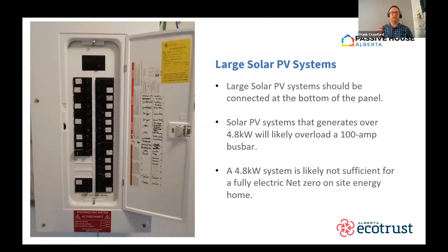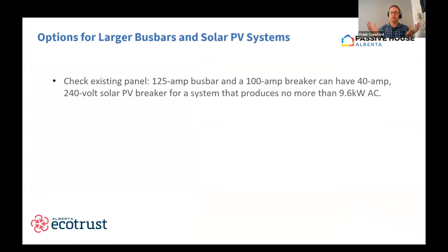Basically, the code clauses say that if you want to attach a solar PV system that generates more than 4.8 kilowatts of AC power, it will overload that 100 amp bus bar. And that 4.8 kilowatts of generation is generally not sufficient to fully electrify a net zero on-site energy home. So we want a larger bus bar for a larger solar PV system. How do we do that? Well, first of all, just check your panel, because lots of panels are actually a 125 amp bus bar, not a 100. So if you just open up your panel, there should be a sticker on it. The sticker's got a whole bunch of numbers. If you see in those numbers 125, it's probably a 125 amp bus bar panel. If you just see 100, it's probably 100 amp.